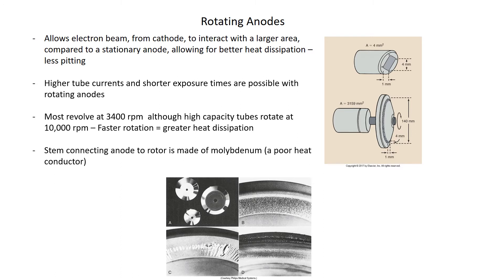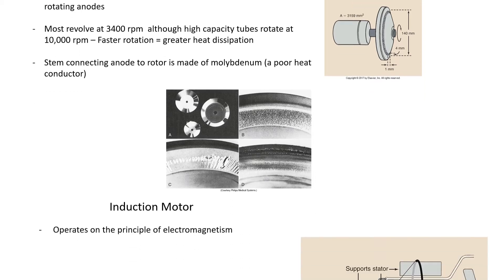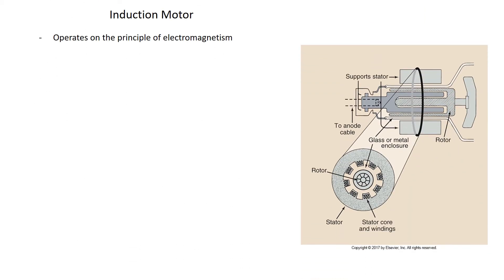The stem connecting the anode to the rotor is made of molybdenum, which is important because molybdenum is a poor heat conductor — you don't want heat to travel from the anode disc into the rotor area. The turning of the disc occurs through what is called an induction motor, which operates on the principle of electromagnetism. You can see a diagram and cross-section of the induction motor that spins the anode.